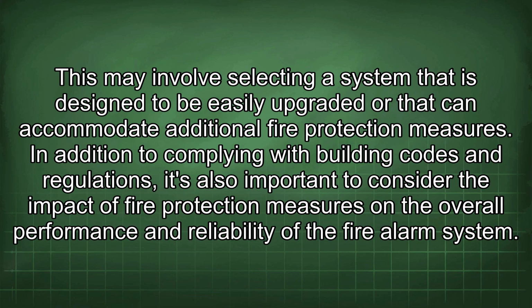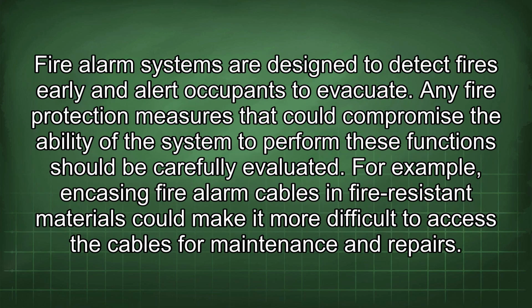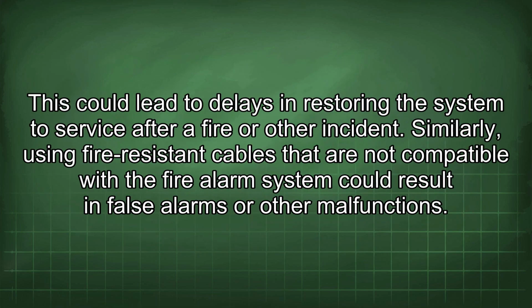This may involve selecting a system that is designed to be easily upgraded or that can accommodate additional fire protection measures. In addition to complying with building codes and regulations, it's also important to consider the impact of fire protection measures on the overall performance and reliability of the fire alarm system. Fire alarm systems are designed to detect fires early and alert occupants to evacuate. Any fire protection measures that could compromise the ability of the system to perform these functions should be carefully evaluated. For example, encasing fire alarm cables in fire-resistant materials could make it more difficult to access the cables for maintenance and repairs. This could lead to delays in restoring the system to service after a fire or other incident.